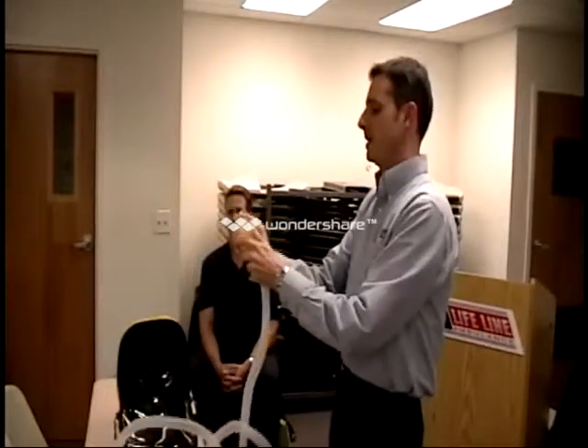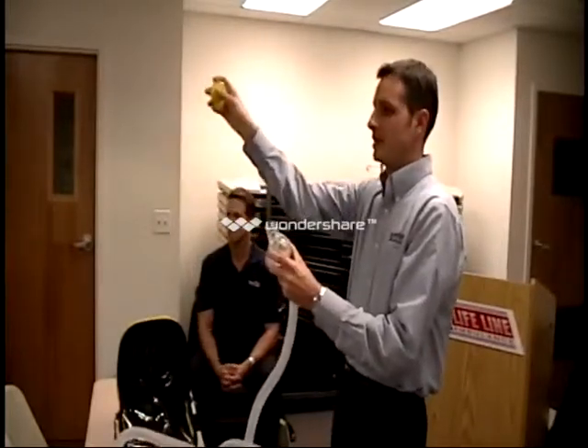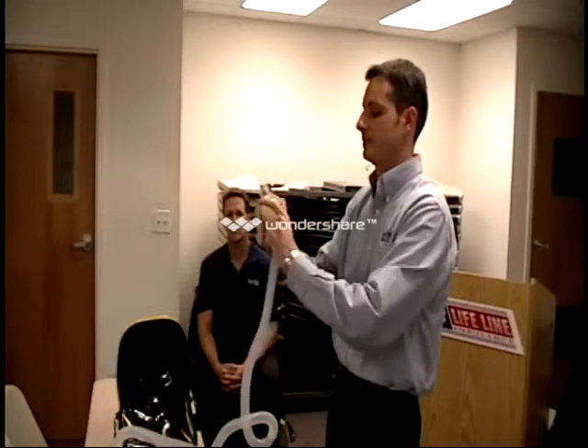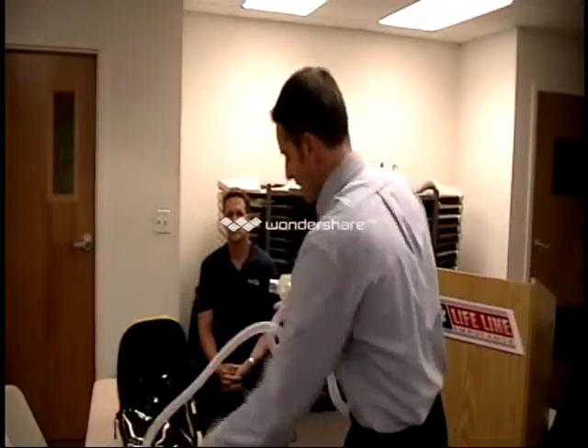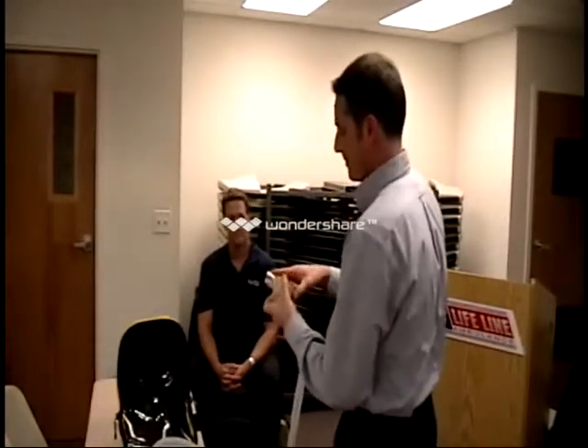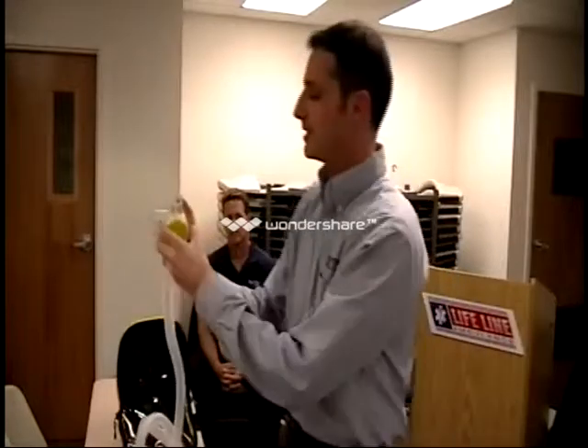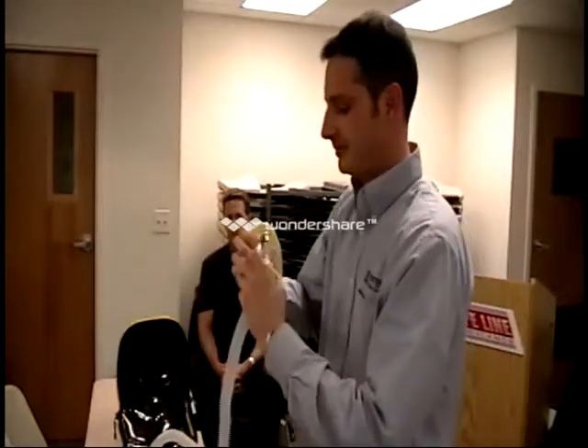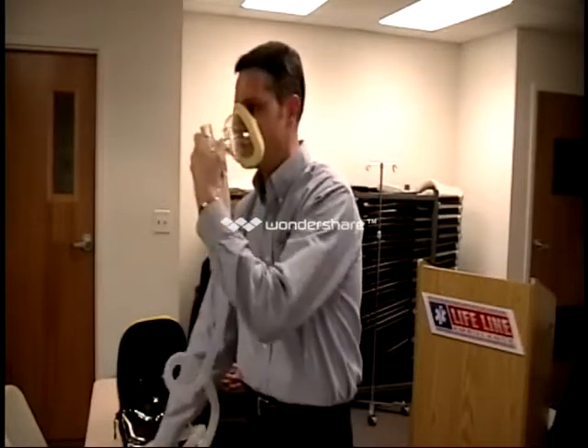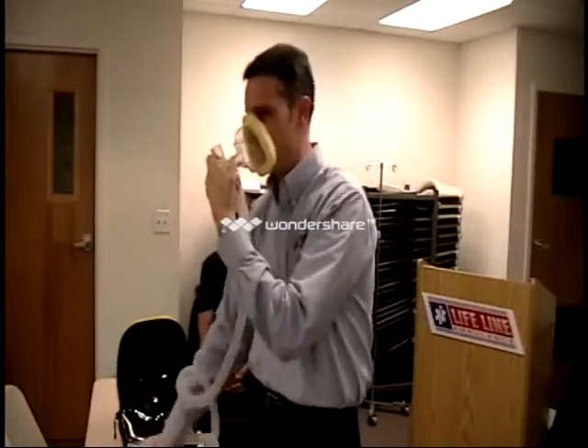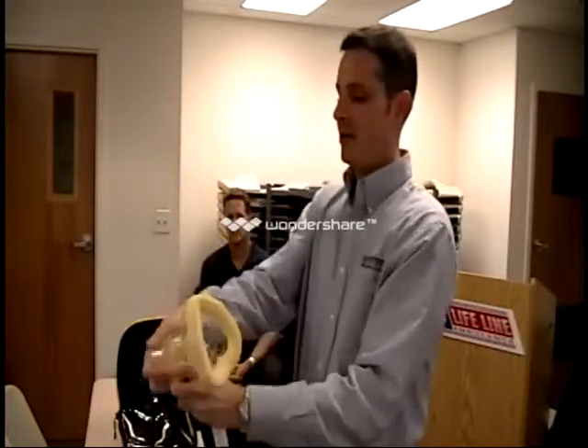Third place this device can continually flow is on this valve here. This exhalation valve opens up as the patient exhales. However, let's say you're putting your capnography on or this gets dropped, this can get dislodged. It falls on the floor on the street next to the cot or something. It takes a pretty sharp blow to do it. This valve will get dislodged here, and what this sounds like is just like this. They're breathing, it's sealed, but it continually flows. If that happens, just pull back a little bit on it. So this little cap untwists, pull back, and make sure it seals on there.